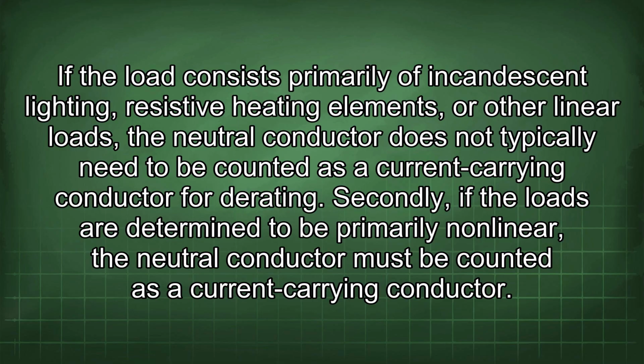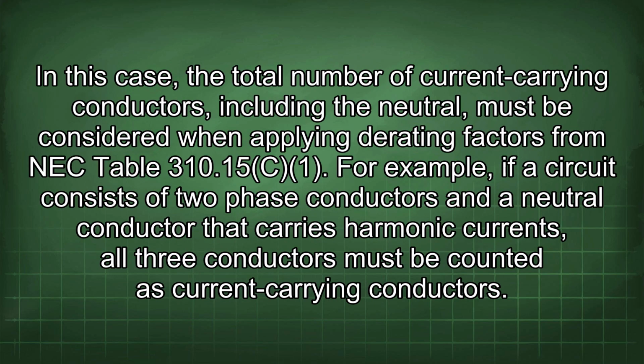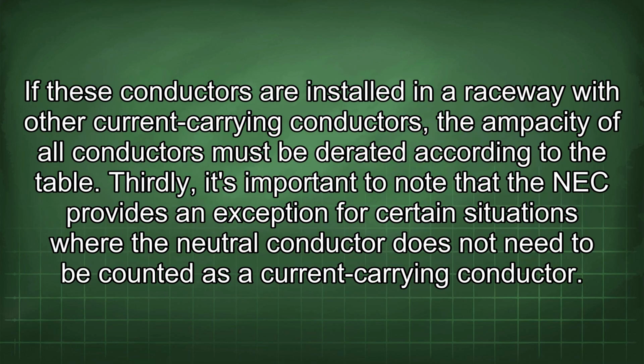Secondly, if the loads are determined to be primarily nonlinear, the neutral conductor must be counted as a current-carrying conductor. In this case, the total number of current-carrying conductors, including the neutral, must be considered when applying derating factors from NEC Table 310.15. For example, if a circuit consists of 2 phase conductors and a neutral conductor that carries harmonic currents, all 3 conductors must be counted as current-carrying conductors.